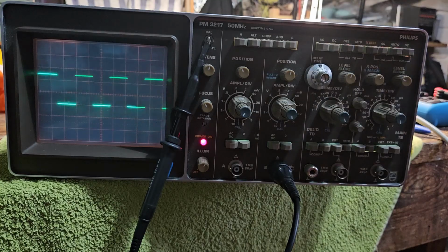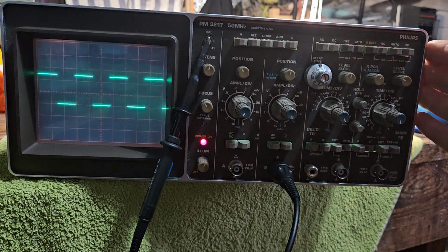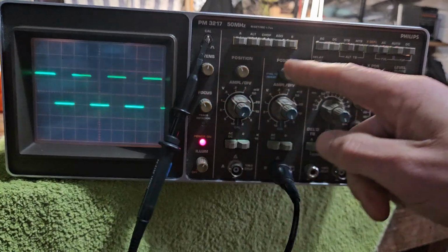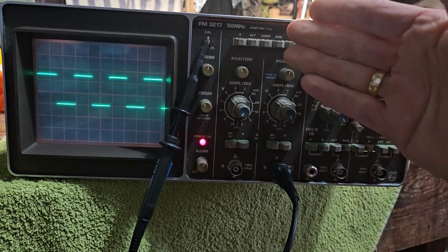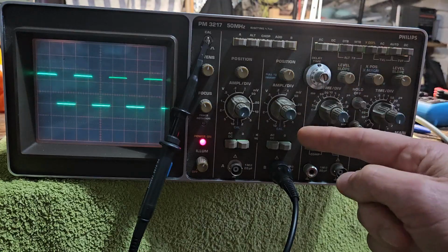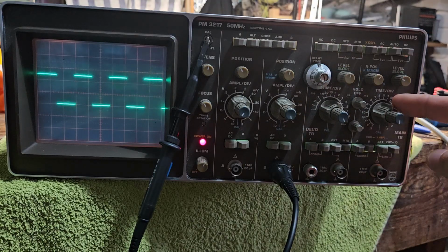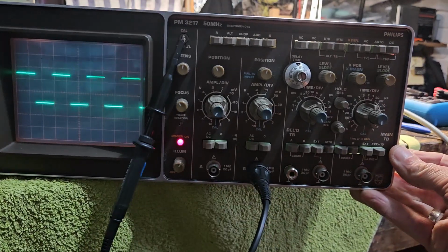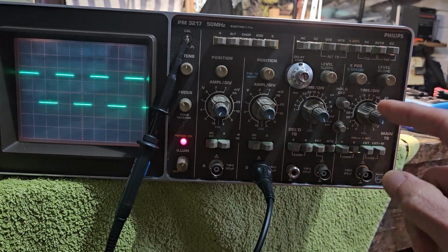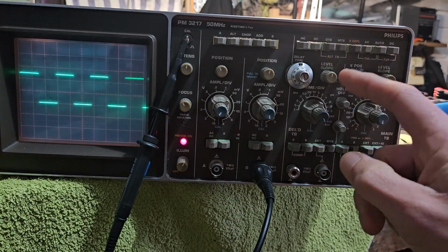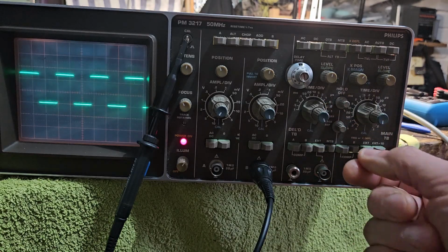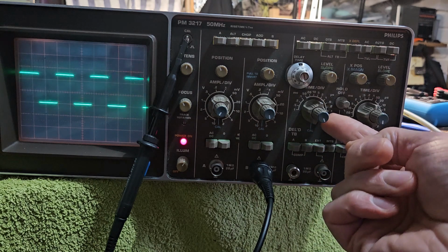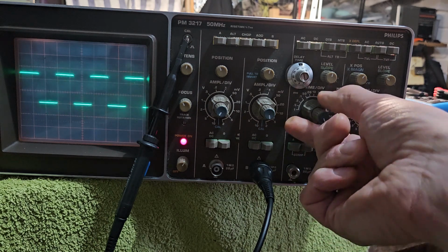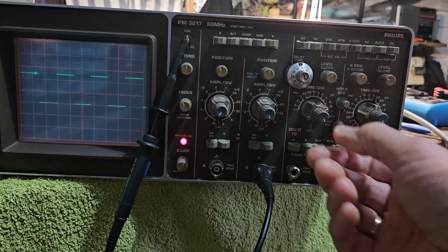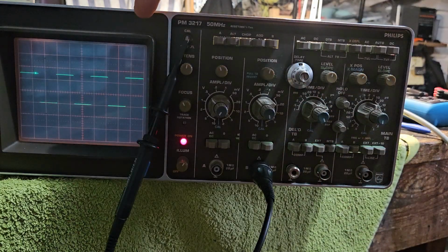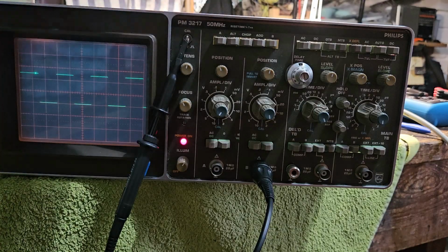But what this does have is a dual time base. So looking at this single channel, we're not going to look at channel A at all in this. Single channel B, normal operation, main time base is controlled over here. So what then is this delayed time base for? Okay, so let's turn it off. Turn it from the off position, and you can see that the main waveform goes dim, but you see a little spot there.